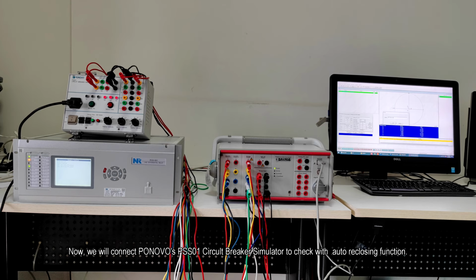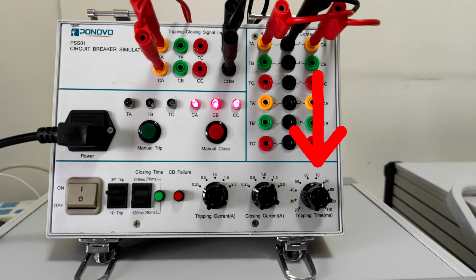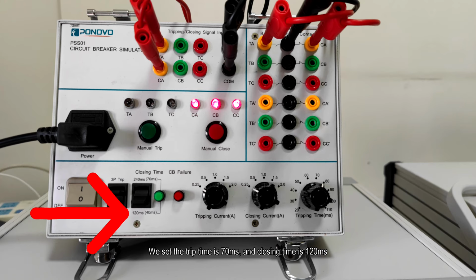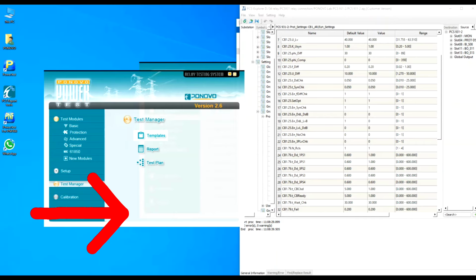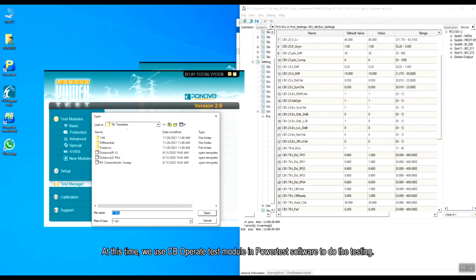Now we will connect PONOVO's PSS01 circuit breaker simulator to check with auto-reclosing function. We set the trip time is 70 milliseconds and the closing time is 120 milliseconds. And this time we use CB Operate in Powertest software to do the testing.